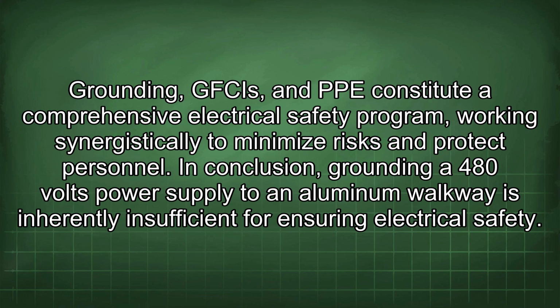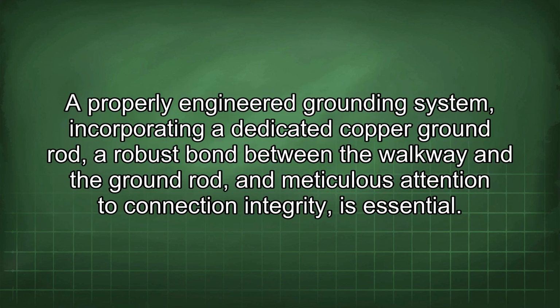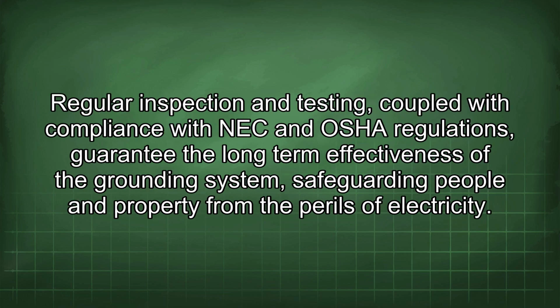In conclusion, grounding a 480 volts power supply to an aluminum walkway is inherently insufficient for ensuring electrical safety. A properly engineered grounding system, incorporating a dedicated copper ground rod, a robust bond between the walkway and the ground rod, and meticulous attention to connection integrity is essential. Regular inspection and testing, coupled with compliance with NEC and OSHA regulations, guarantee the long-term effectiveness of the grounding system, safeguarding people and property from the perils of electricity.